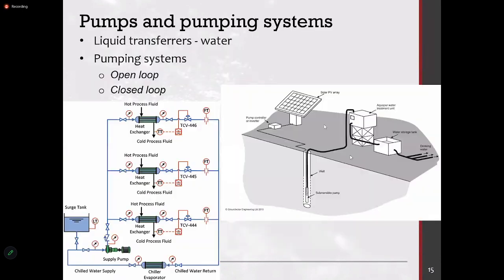Sometimes they are not marked, and you'll have to look at manuals and catalogs to see what the pump power actually is. So generally for this type of open loop system, pumping water to the overhead tank, we call it a transfer pump in building services terminology. So the key is you have to have the head. Head is a must. So your head will be this.